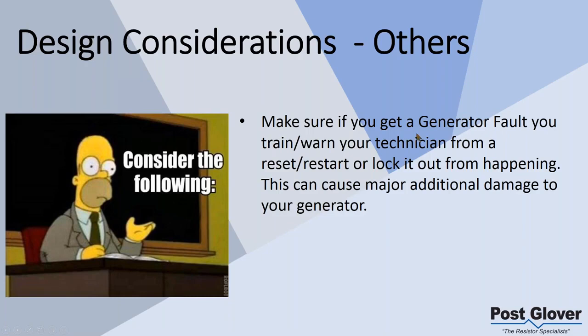So based on this, it has to do with your personnel. You want to make sure your technician or whoever's operating the generator understands that when you have a stator fault, you're damaging your generator, essentially. That's the definition of a stator fault, essentially. So the longer you operate that generator, the more damage you're going to have. A lot of times, if a technician had an issue, they realized that the generator was stopped, maybe they would try to reset it, restart it. That's not something you want to happen in this scenario. So if you have a differential relay, you may want to lock it out. There may be some training or whatever it's going to be. You need to make sure that there's a way that that technician knows that he's not to try to restart this.